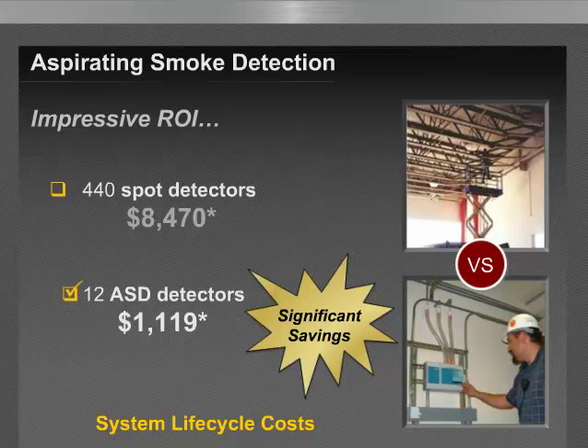And so you take the 440 spot type detectors, each requiring to be accessed for test and inspect, particularly in a datacom type infrastructure, which may present some challenges in terms of accessibility. Nonetheless, you take each and every detector, you make some assumptions in terms of labor costs and time to test and inspect each sample port, and you compare that. You come up with $8,470, which is quite conservative from that perspective.